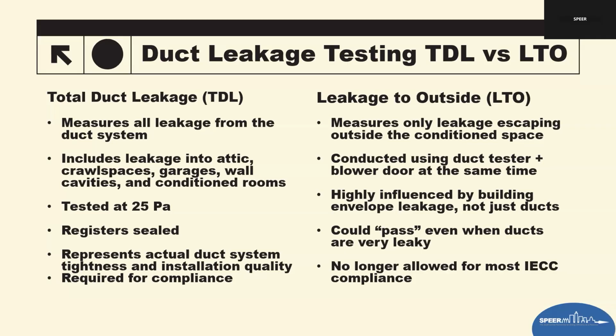So on the left side, we see a breakdown of what TDL is. Total duct leakage basically measures everything leaking in the duct system, no matter where the air is going. This test captures leakage into attics, crawl spaces, garages, between floors, wall cavities, even in the conditioned room. It's performed at 25 pascals with all registers sealed, and the test isolates the duct system itself and the unit and equipment. TDL is the only test method that reflects the actual installation quality of the duct system.